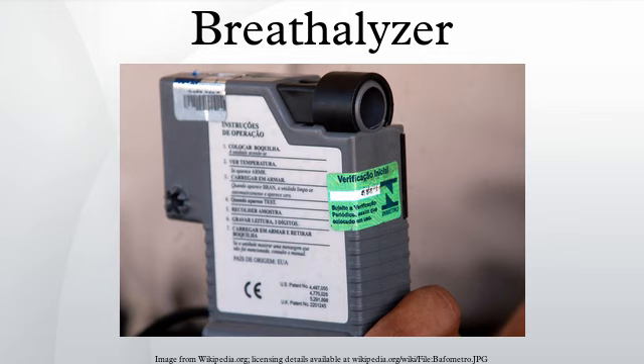On the other hand, products such as mouthwash or breath spray can fool breath machines by significantly raising test results. Listerine mouthwash, for example, contains 27% alcohol. The breath machine is calibrated with the assumption that the alcohol is coming from alcohol in the blood diffusing into the lung rather than directly from the mouth, so it applies a partition ratio of 2100-to-1 in computing blood alcohol concentration, resulting in a false high test reading.